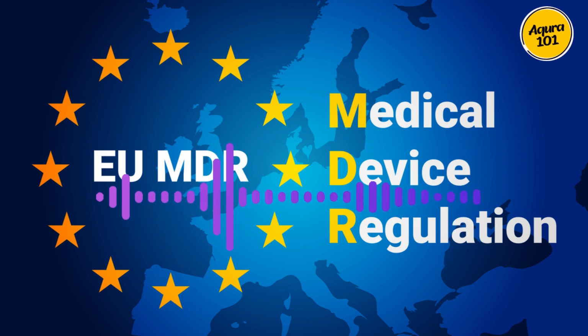What kind of investigation are we talking about? The MDR requires manufacturers to determine the nature and cause of the complaint, evaluate whether the complaint suggests a serious incident that needs to be reported to the competent authorities, and take appropriate corrective actions if necessary. This might involve making changes to the device's design, its manufacturing process, or its labeling. It could even lead to a recall of the device if a serious safety issue is identified. It's all about taking complaints seriously and using them as opportunities to improve device safety and quality.